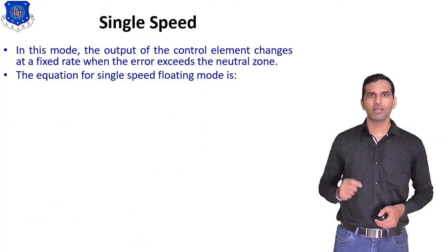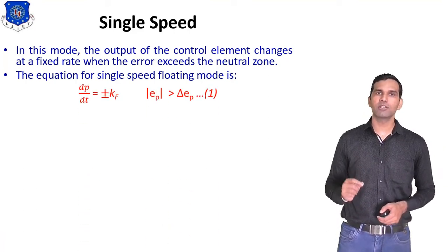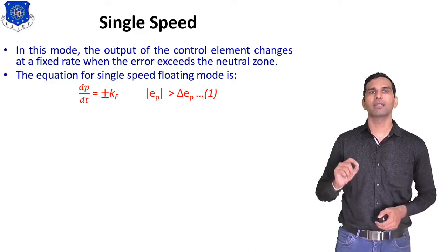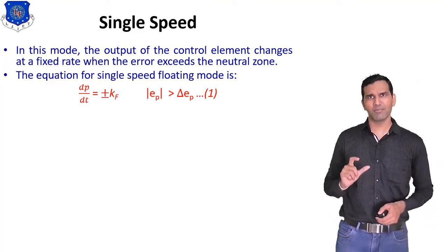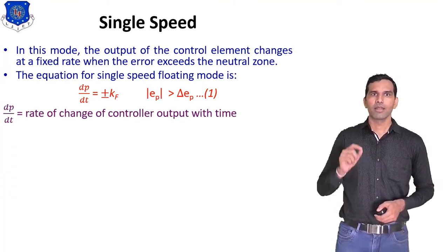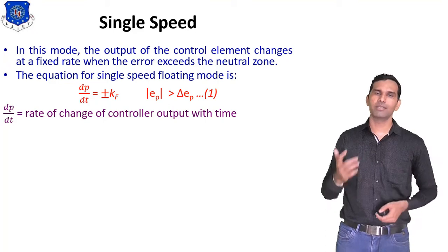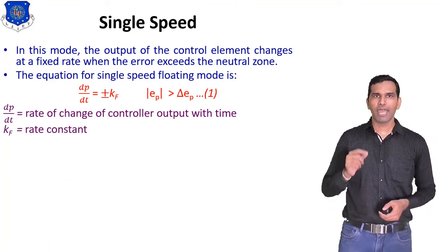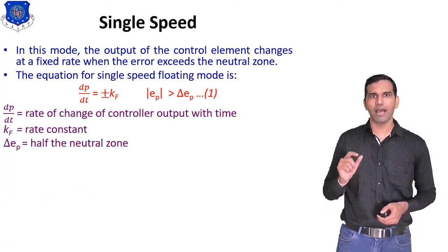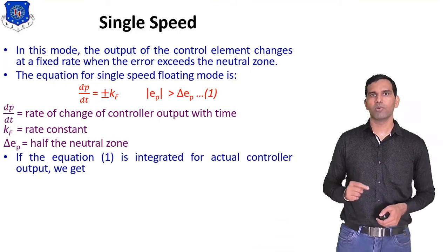The equation for single speed floating mode is: dp/dt = ±Kf, where ep > Δep. This is the mathematical representation. Here, dp/dt indicates the rate of change of controller output with time, Kf indicates the rate constant, and Δep indicates half the neutral zone.